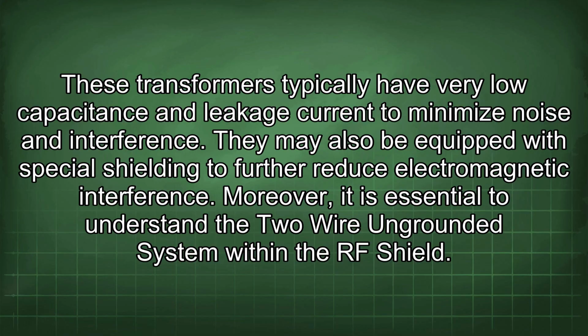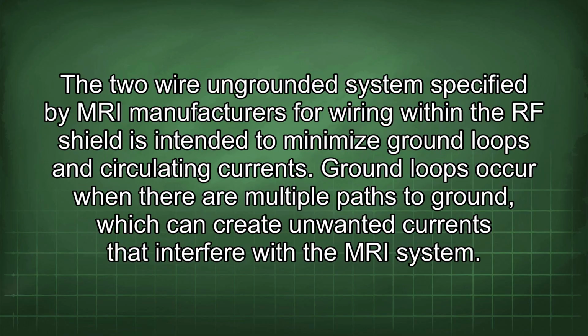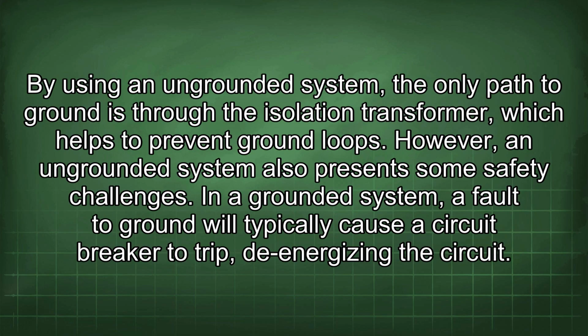Moreover, it is essential to understand the two-wire ungrounded system within the RF shield. The two-wire ungrounded system specified by MRI manufacturers for wiring within the RF shield is intended to minimize ground loops and circulating currents. Ground loops occur when there are multiple paths to ground, which can create unwanted currents that interfere with the MRI system. By using an ungrounded system, the only path to ground is through the isolation transformer, which helps to prevent ground loops. However, an ungrounded system also presents some safety challenges.